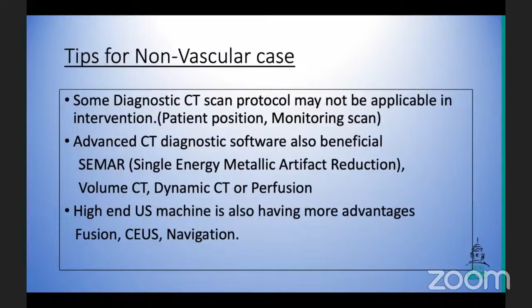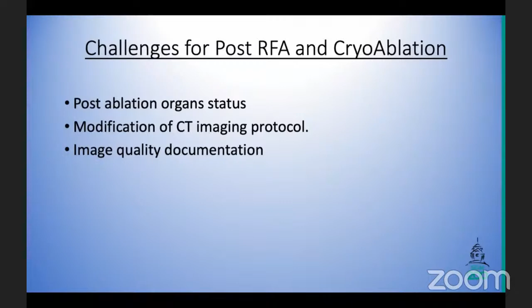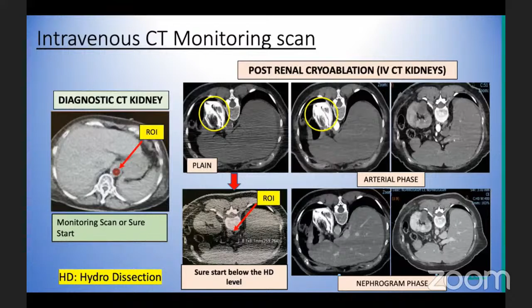Challenges for post-RFA and cryoablation, modifications of CT imaging protocol, and image quality documentation. So this is the one I'm referring to for diagnostic CT. This is a useful monitoring scan or Sure Start ROI positioning. But for post-cryoablation, sometimes it is not ideal because of some hydrodissections. So it was decided to position the monitoring scan beyond the hydrodissection.